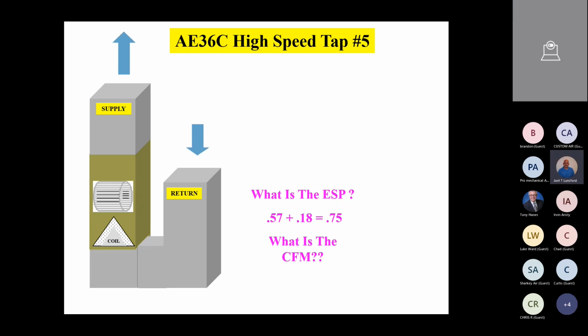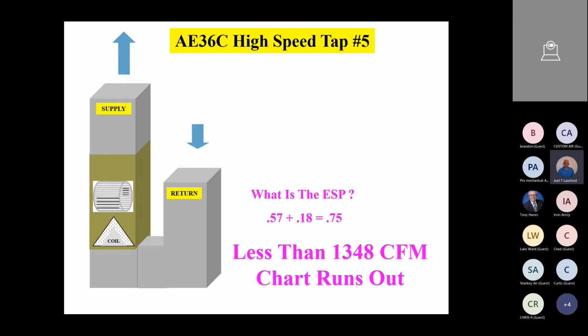I'm glad that the mics are kind of muted, because the truth is the chart runs out again. We know the airflow is less than 1348 because that's where the chart runs out. And so I just wanted to do one more example of this. If you have a sample or an example where you have a duct system and you're in there measuring airflow, you say, daggone, the chart runs out, you've got a problem. And so by taking those pressures individually, again, you can tell quickly which side it is on, supply or the return side of the duct system.